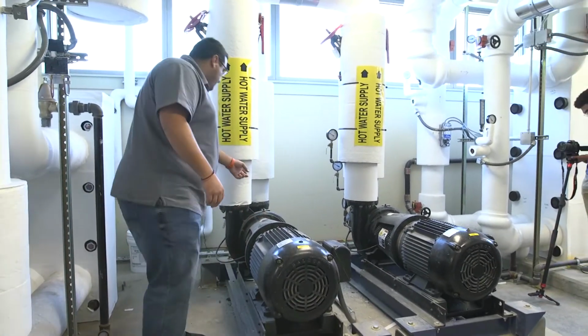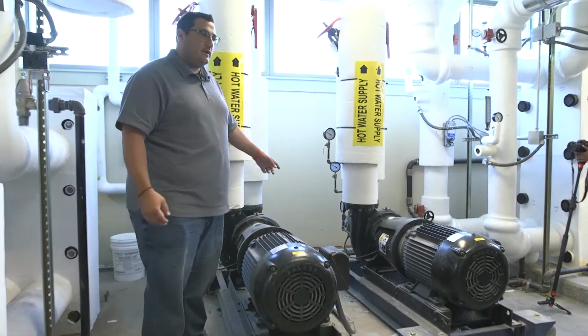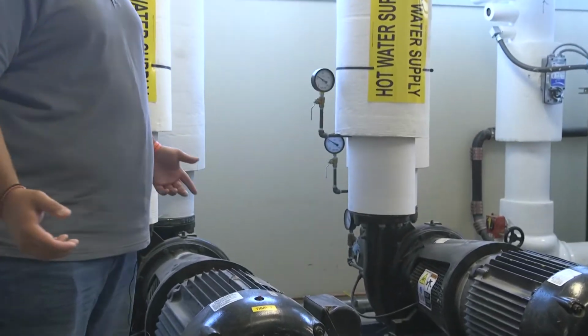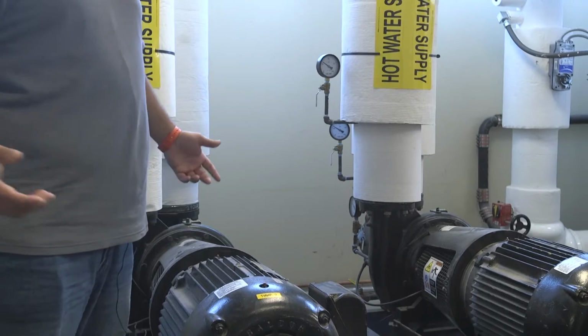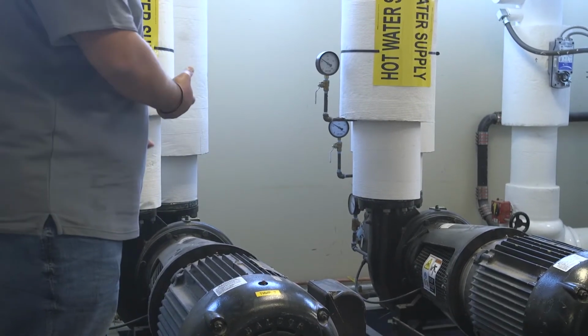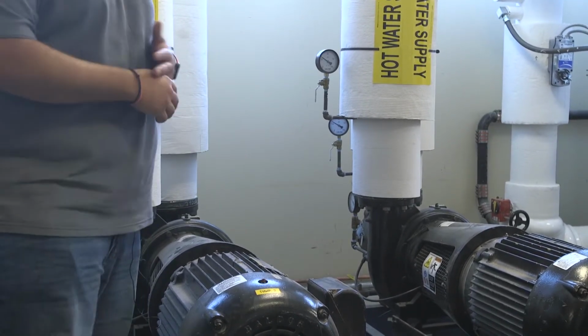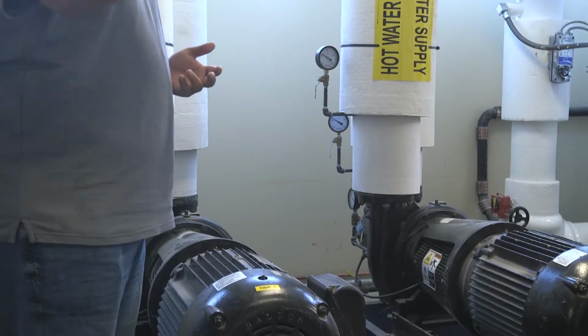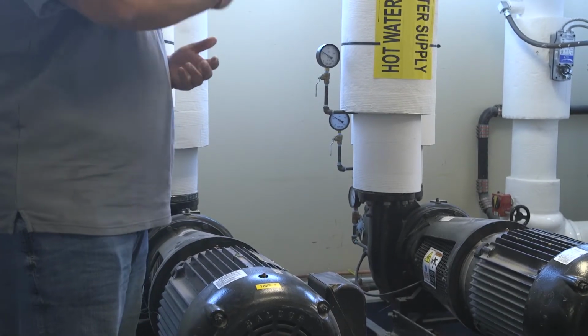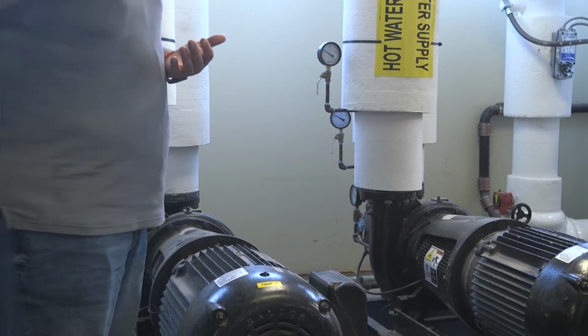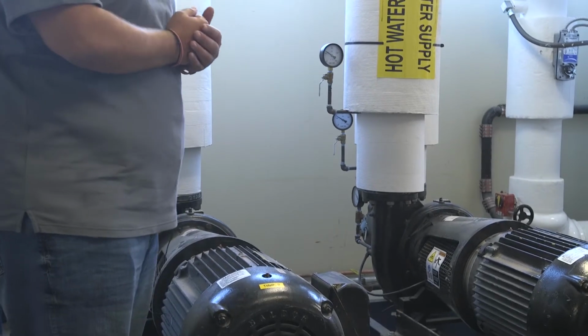Occasionally you have some strainers here on the end. Depending on how dirty your system is, those need to be cleaned to get out all the stuff for the most efficient pump operation. However, again, when you do drain and clean the strainers, you have to remember to evacuate the air and prime the pumps afterwards.